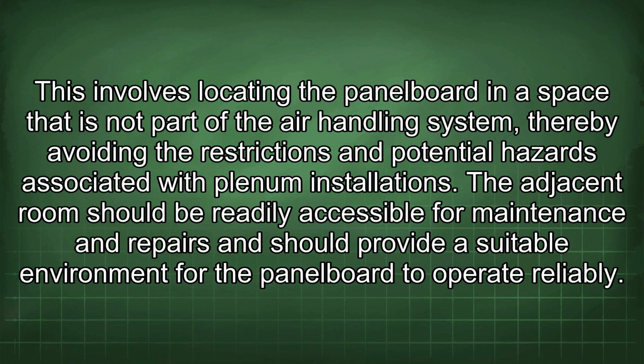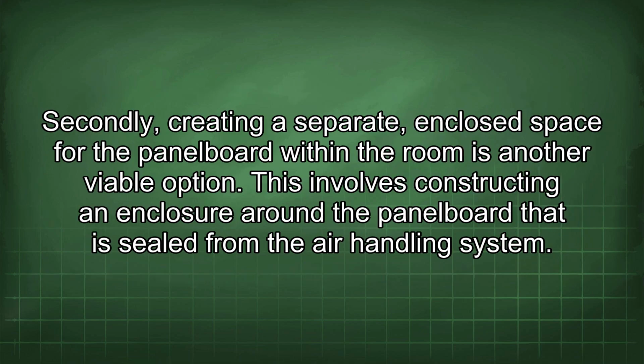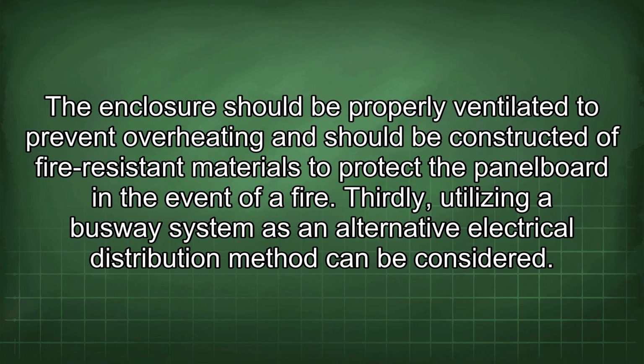Secondly, creating a separate, enclosed space for the panel board within the room is another viable option. This involves constructing an enclosure around the panel board that is sealed from the air handling system. The enclosure should be properly ventilated to prevent overheating and should be constructed of fire-resistant materials to protect the panel board in the event of a fire.